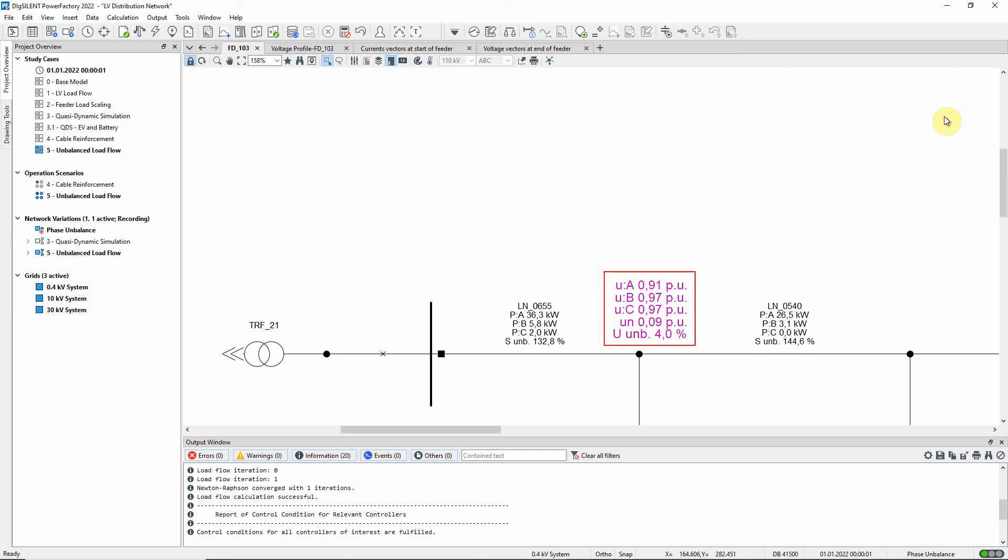For the terminals, we can see the voltages of all three phases and the neutral conductor to earth, together with the imbalance factor of the voltage. This factor reflects the ratio between negative and positive sequence voltages and is quite large in this case.